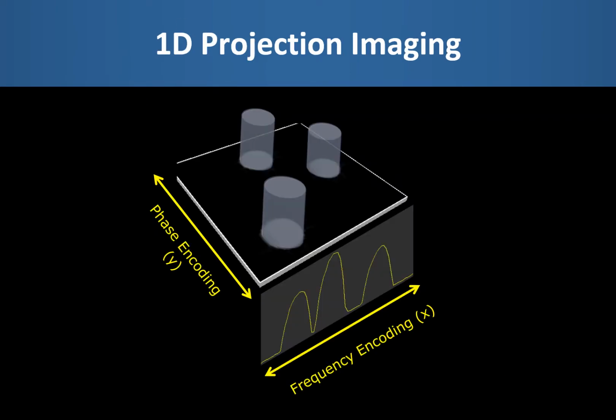We shall now look at the standard method for MRI in-plane spatial encoding that was called spin warp by the inventors at the University of Aberdeen back in the early 1980s. We shall see later the relevance of the warp, sadly entirely unrelated to speed. This method names the two in-plane directions the frequency encoding and the phase encoding.